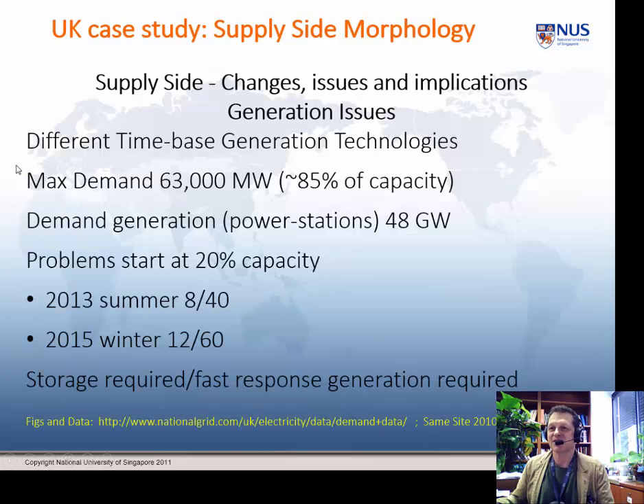So let's think about this. These numbers you've already seen. Power stations of the 63,000 megawatts, which is 80-odd% of capacity, demand generation is 48 gigawatts. That means the stations you've got, you're already planning for that, that's fine. Anything above that begins to be a problem and is called peak. In 2013 and in 2015, the contribution of wind to the UK national grid caused problems of those types, because the amount of storage required, and fast response storage, was, to be blunt, more than was available.